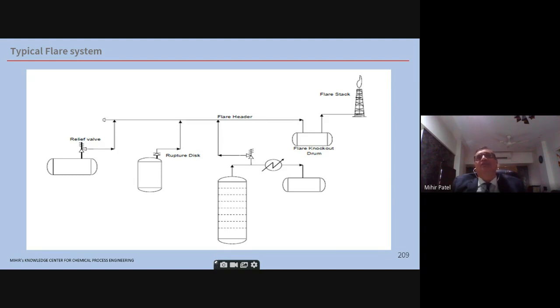There are pilots on the flare burners. These pilots have to be continuously operated. In large refineries, there is no issue, but in small plants, let's say you have a flare which is mandatorily required, they also have an LPG backup system. So that can supply as a backup to the flare pilots basically.